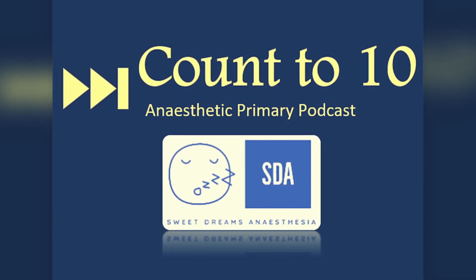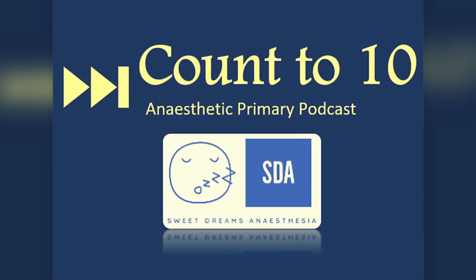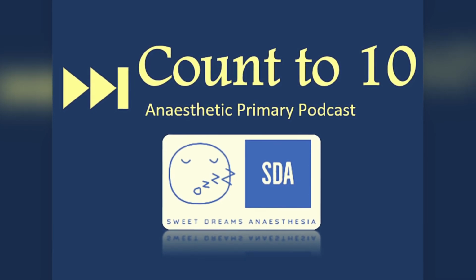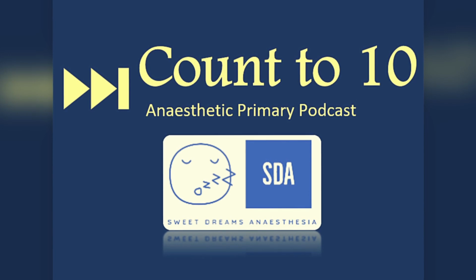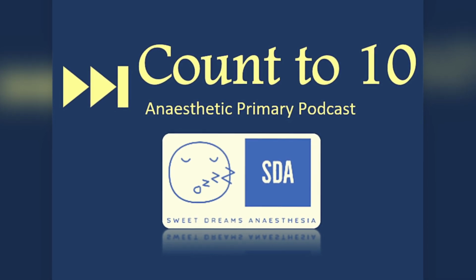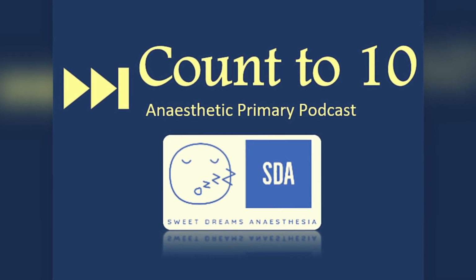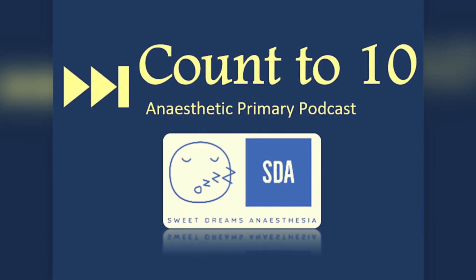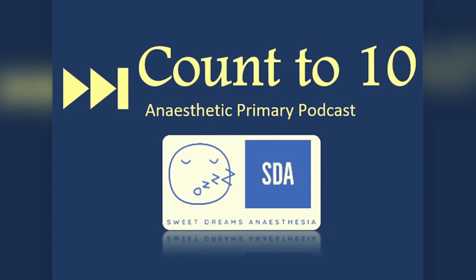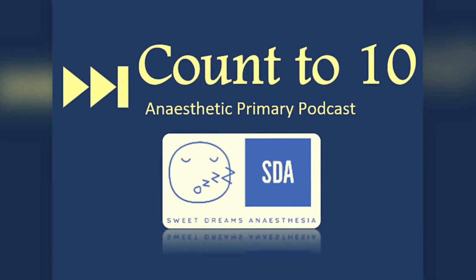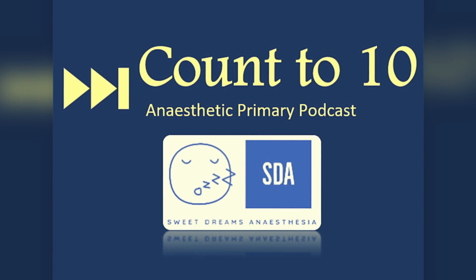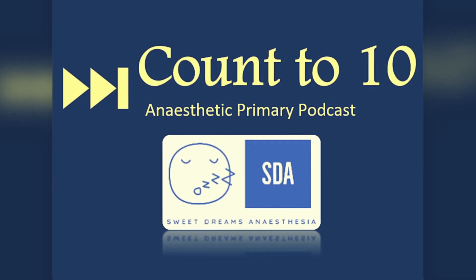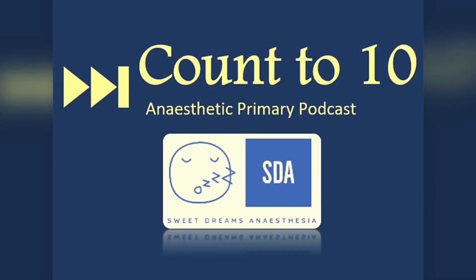The disadvantage of using a gas dilution method is that only ventilated units of the lungs are measured, because only ventilated units of the lungs are getting that oxygen and expiring that nitrogen. What it doesn't take into account for is diseased lungs and lungs that might have some gas trapping, and so therefore those volumes aren't measured, and therefore we get an underestimation with gas dilution methods.